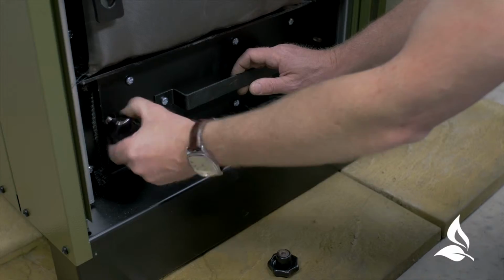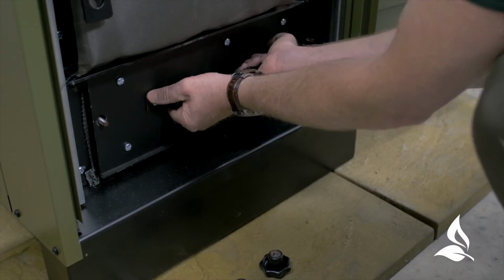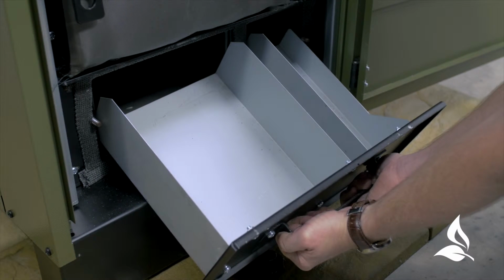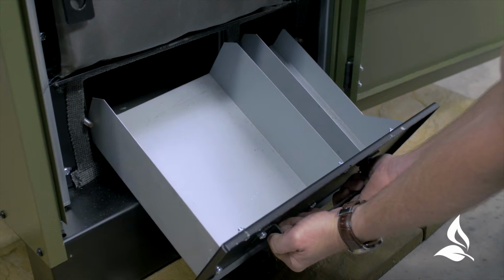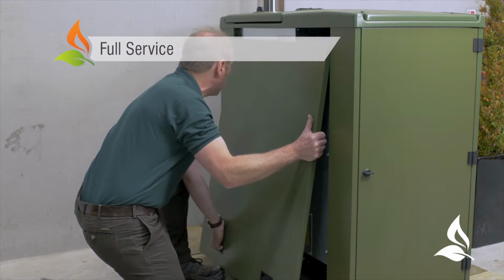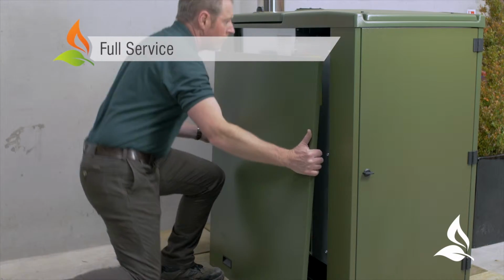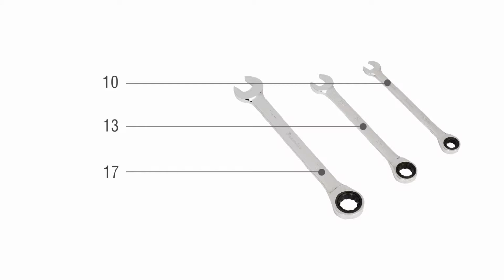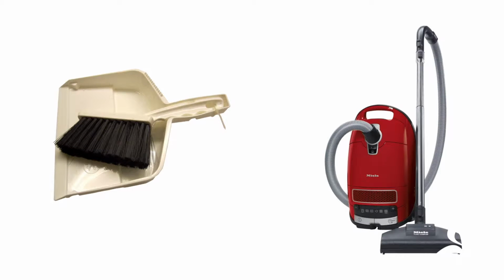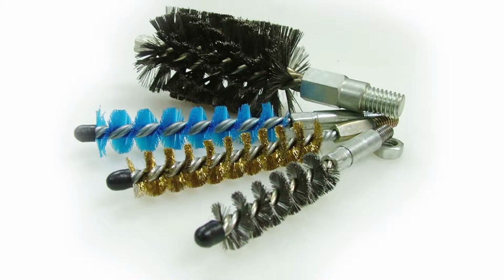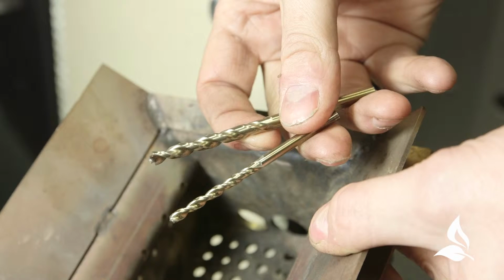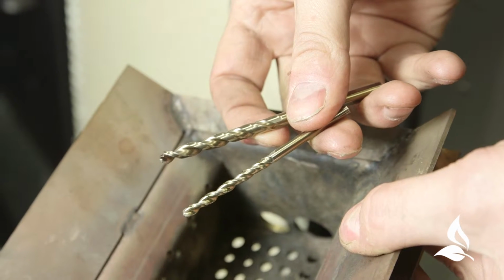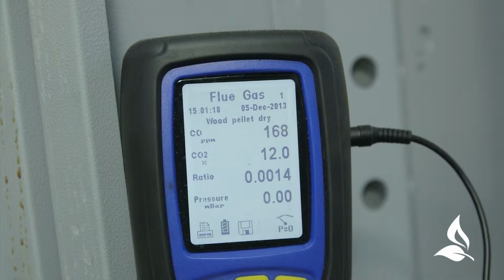The end user also has a part to play in regularly emptying the ash pans and giving the heat exchanger a clean down periodically. This is covered in more detail in the quick guide booklet enclosed with each boiler. Full service. The service engineer has a number of tasks to complete as part of the full service. Tools that the service engineer will require are 10, 13 and 17 spanners, a brush and vacuum cleaner, brushes to clean the flue, a drill with 4mm and 5.5mm bits, and a flue gas analyzer.